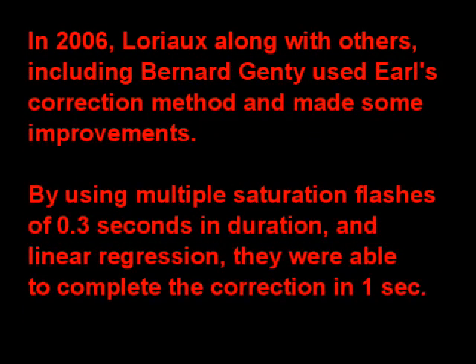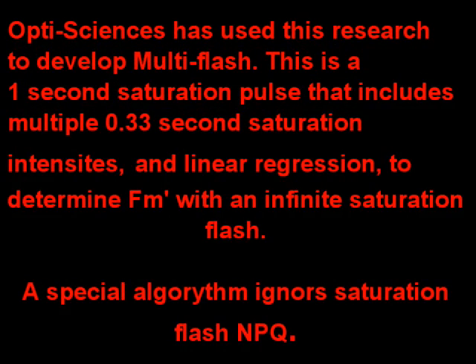In 2006, Loriaux, along with others including Bernard Genty, used Earl's correction method and made improvements. By using multiple saturation flashes of 0.3 seconds in duration and linear regression, they were able to complete the correction in one second. OptiSciences has used this research to develop multi-flash: a one-second saturation pulse that includes multiple 0.33-second saturation intensities and linear regression to determine FM prime with an infinite saturation flash.